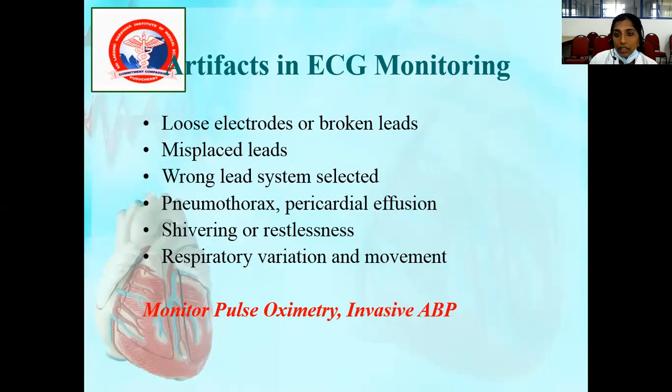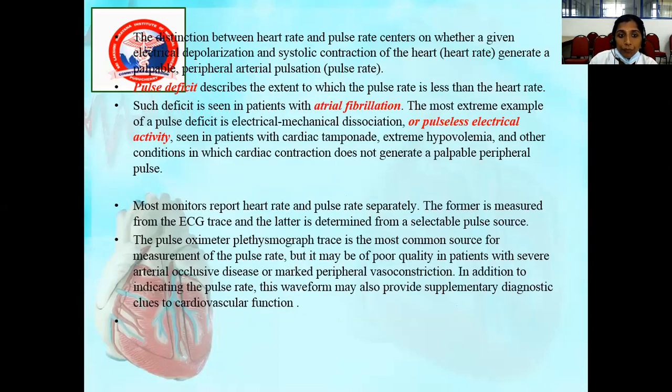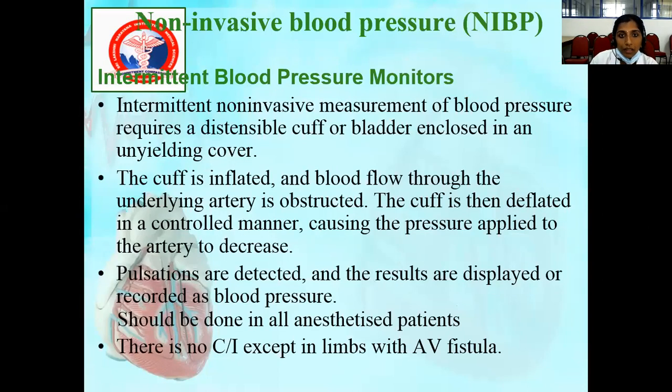Again, in ECG also, we can have artifacts, like you can have a loose or broken electrode, or misplaced, wrongly placed leads. And if the patient is shivering or restless, at that time, these can affect it. So that was about the ECG.